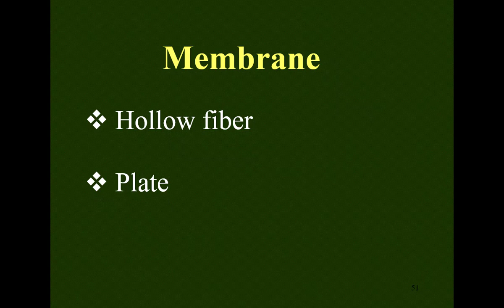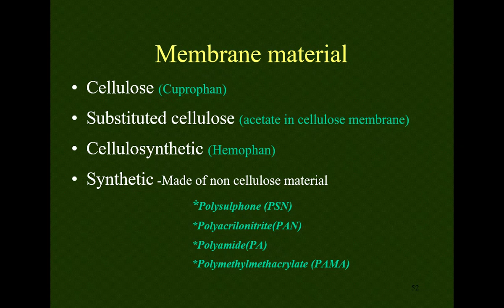Membrane can be hollow fiber or plates. There are different membranes too, from cellulose to purely synthetic and semi-synthetic. The importance here is that a synthetic is more biocompatible. The issue that arises is that sometimes we come across bioincompatibility, where the system causes a problem to the patient: activation of complement, coagulation cascade and leukocytes.